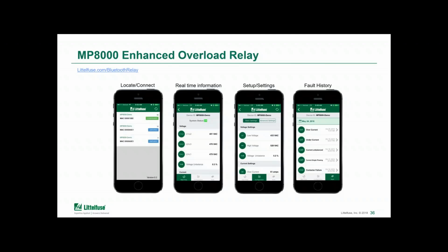So in many cases, that actually opens the door to have more insight into the history of the relay, into some of the actions and trip events, just because you can display that information in more flexible ways in the app. So here there's a few screens just as an example relating to that MP8000 relay. And as you can see here, it still has the ability to see the real-time measured values, change the settings, and view the fault history. So all of that flexibility still remains, combined with the safety of not having to open the panel door.